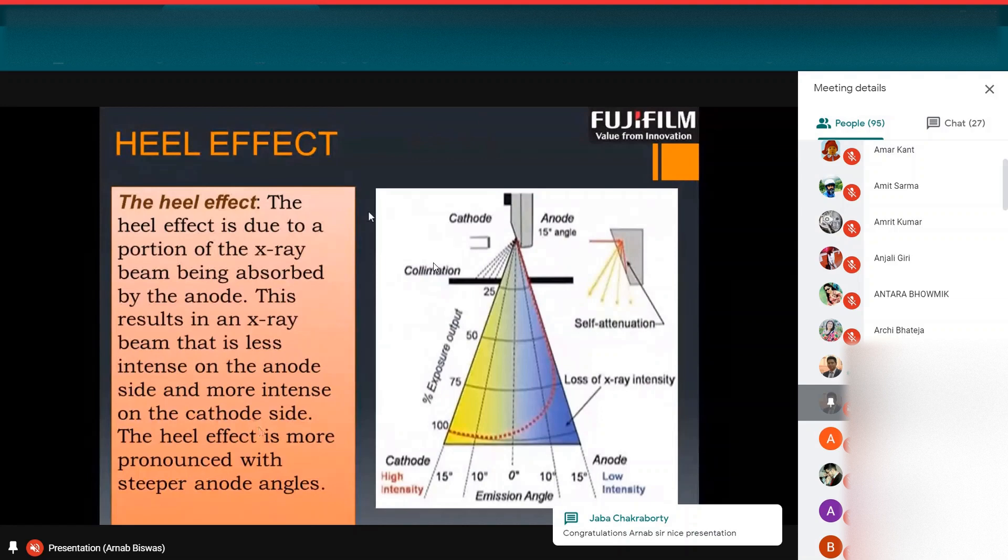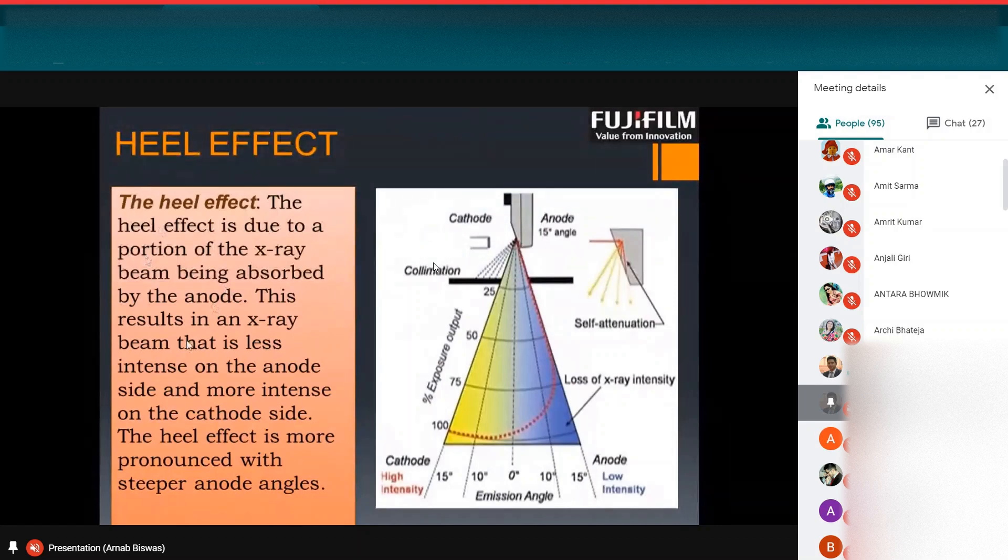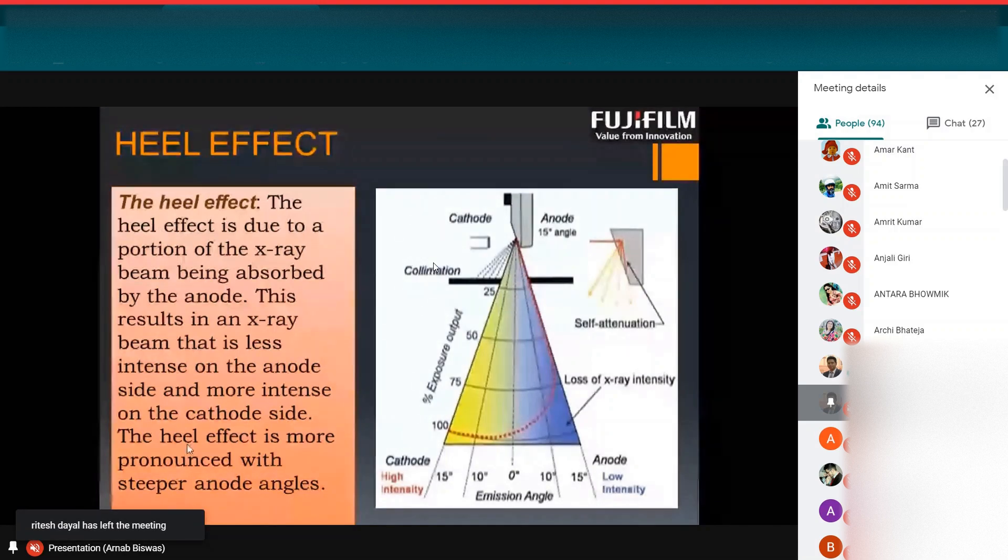What is heel effect? The heel effect is due to a portion of the X-ray beam being absorbed by the anode. This result in an X-ray beam that is less intense on the anode side and more intense on the cathode side. The heel effect is more pronounced with steeper anode angles.